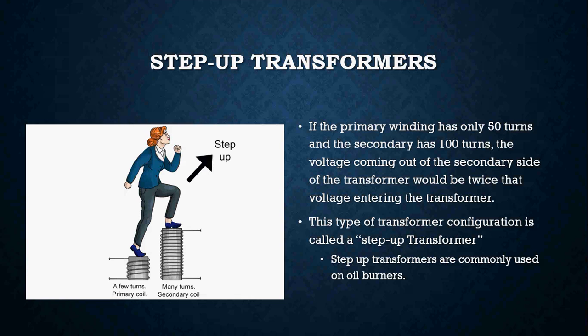Step-up transformers are really just the opposite. The primary winding may have 50 turns, but the secondary winding will have 100 turns, so the voltage coming out of that secondary side would be twice the amount entering. You're going to see step-up transformers on oil burners — we use them to send electricity to the electrodes, which will ignite the oil. Typical oil burner step-up transformers may have a 120-volt primary and step up to about 10,000 to 14,000 volts, which is achieved by having more windings on the secondary side.